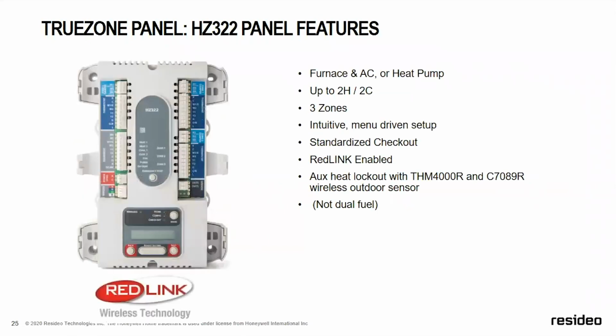HZ322, furnace, AC, or heat pump. It's 2 heat, 2 cool. Again, 3 zones. It is an intuitive menu-driven setup. Standardized checkout, which means that when you commission this panel, you can check out your zones, you can check out your heat cycle, you can check out your cool cycle. Understand when you do a checkout though, you are bypassing safeties. So you want to be careful when you're doing a checkout.